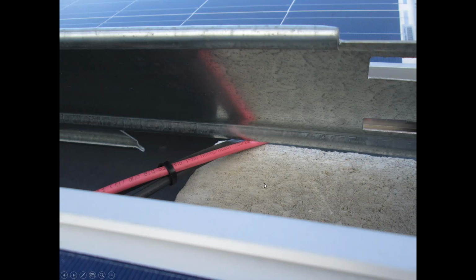This next slide you'll see here, this is a ballast block. You've seen these in a few other photos, but basically it's a concrete paver. And up in this area, the most common installation method on a flat roof would be what's called the ballasted PV system. So typically not on high rises, but on the lower one, two, maybe three-story rooftops, we'll see this. These concrete pavers hold the array down to the roof.